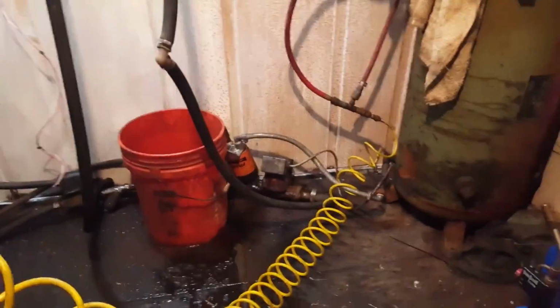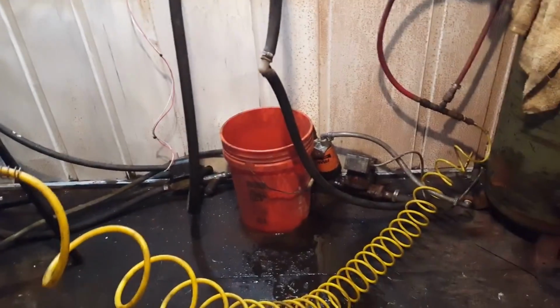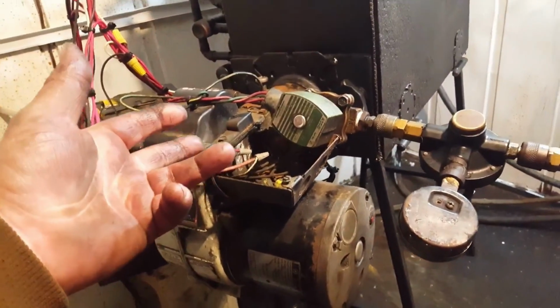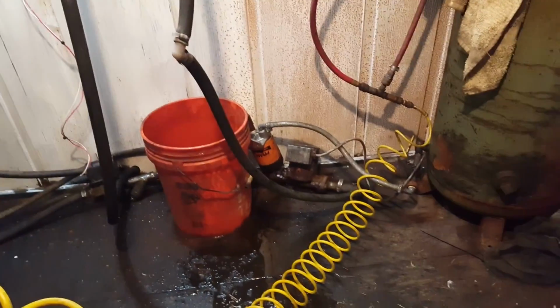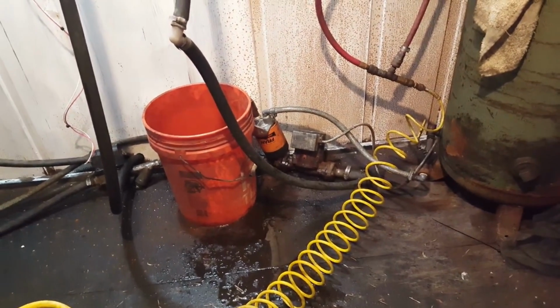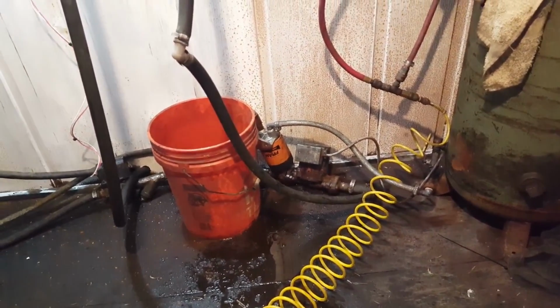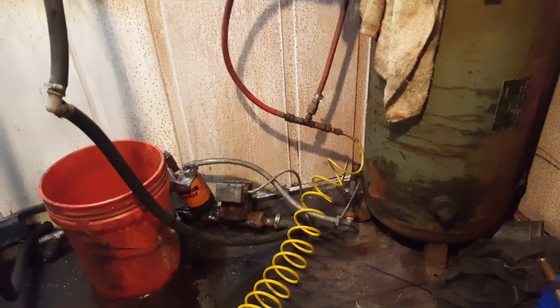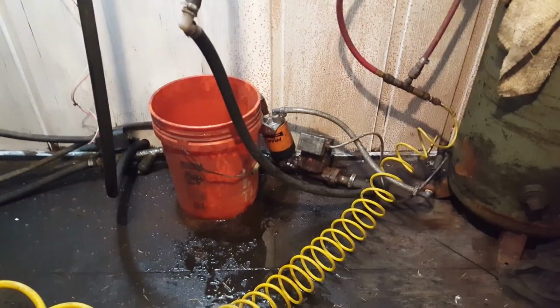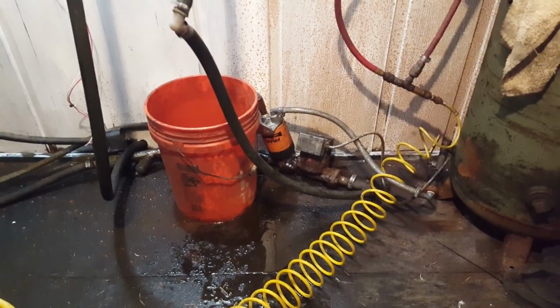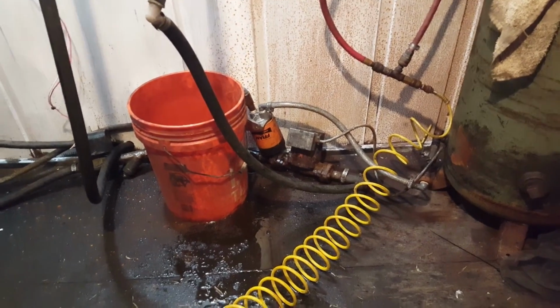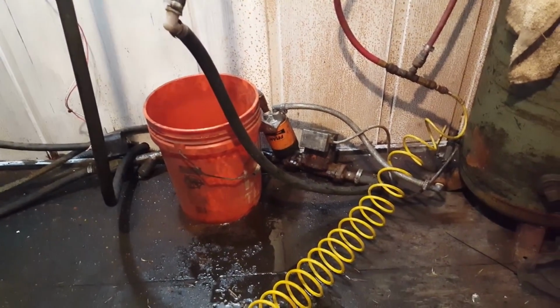I forgot to tell you, another safety measure: if it does get shut down, either due to no water flow, over temp, or if it loses the flame sensor, I've got it set for that pump to run 10 or 15 minutes, I can't remember. That's in case it does over temp - I want it to keep circulating and cool the water down. If you just shut the pump down at 180 degrees while it's boiling the water, it's going to blow something, a hose or something.